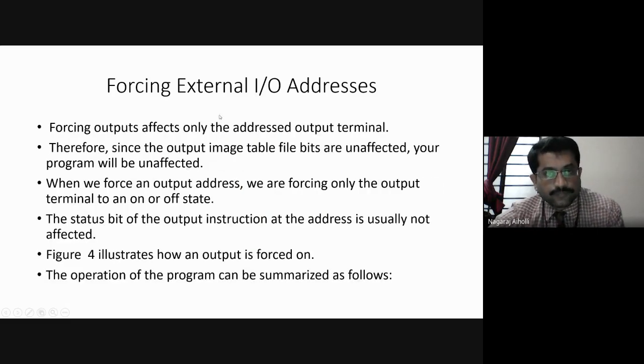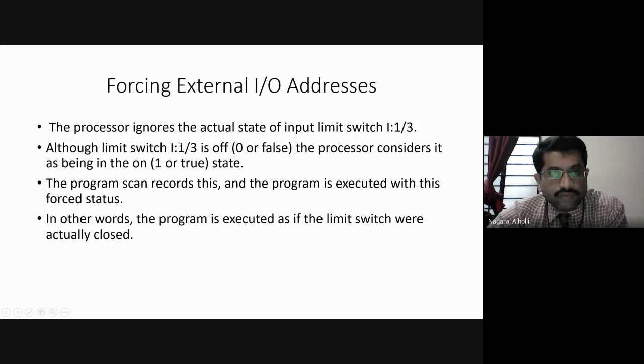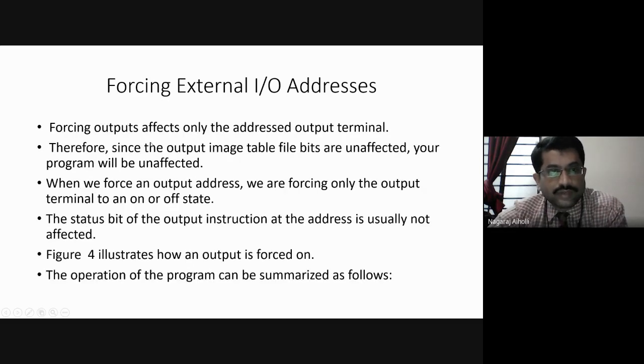Okay, next is forcing external I/O addresses, that is, forcing outputs. First, we forced the input field device. Next, we are forcing the output field devices. Forcing outputs affects only the addressed output terminal. Whichever output terminal we want to change, only that device state will be changed from on to off or from off to on state. Other devices' status will not be affected. Therefore, since the output image table file bits are unaffected, your program will be unaffected.